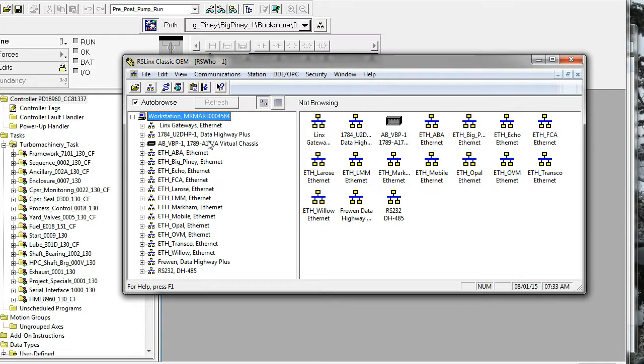That is how you configure a topic in RSLinx to connect to a PLC. One comment about RSLinx: you have to be running something other than the Light version — Classic OEM in my case, or a Gateway, or any version of RSLinx that supports an OPC server. The Light version of RSLinx comes as part of ControlLogix or any logic editing package you purchase, but the light version doesn't support OPC server.